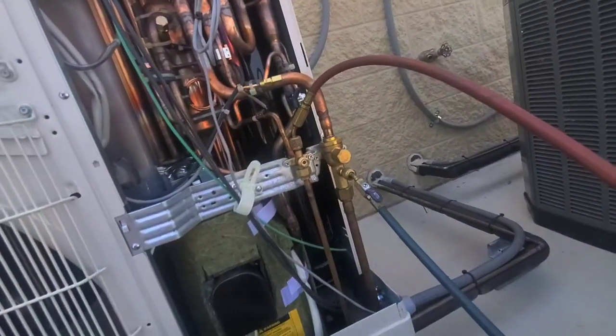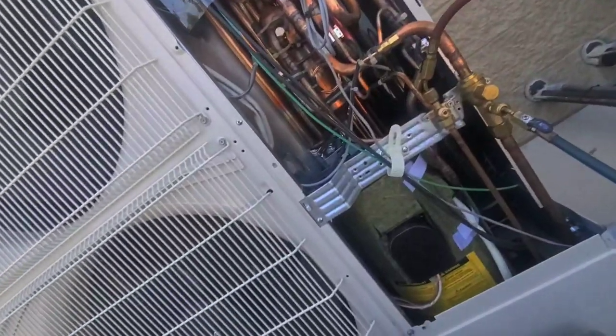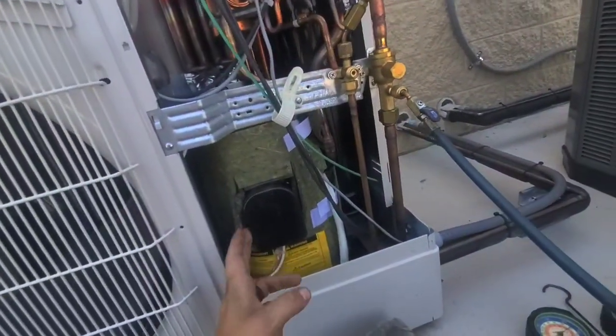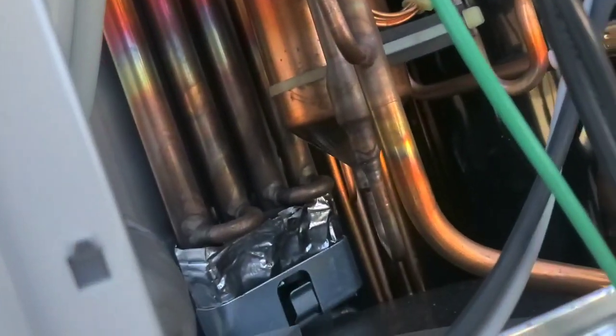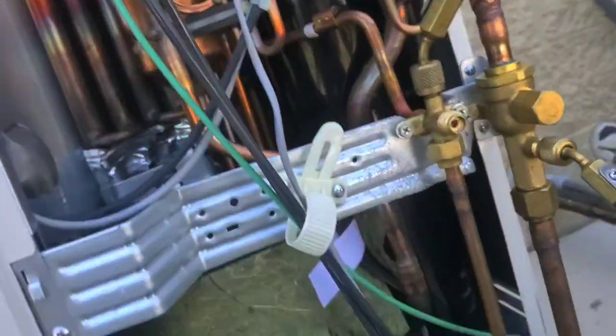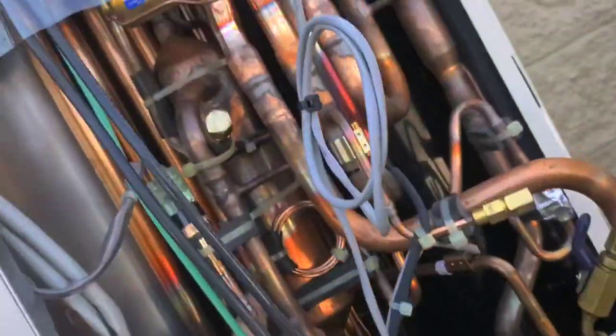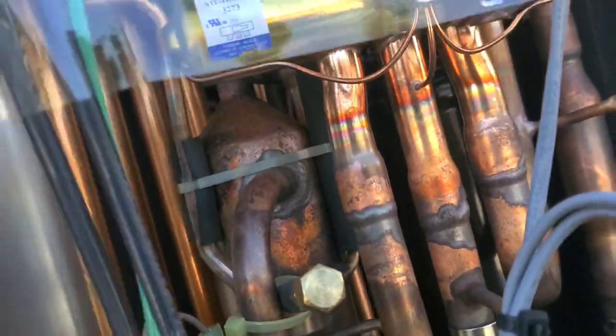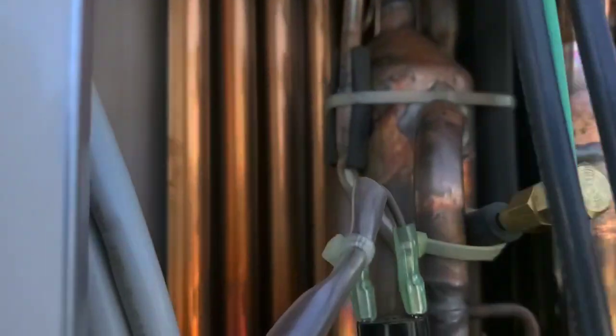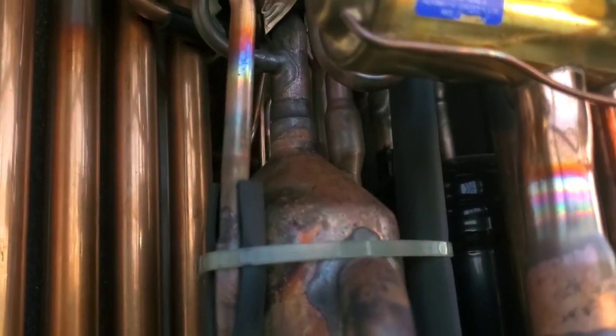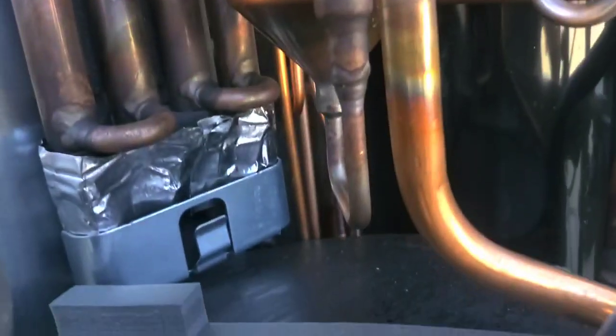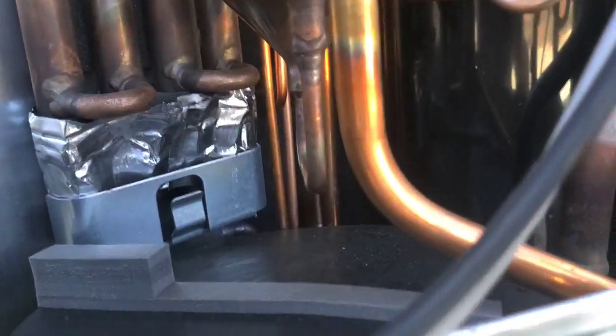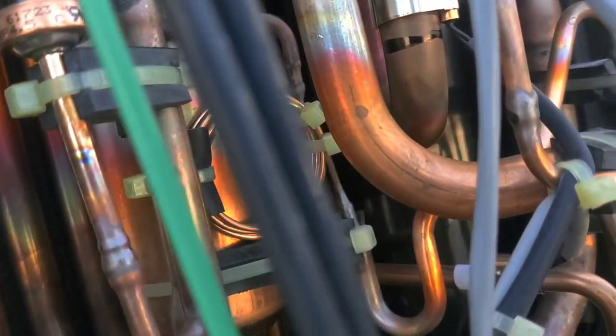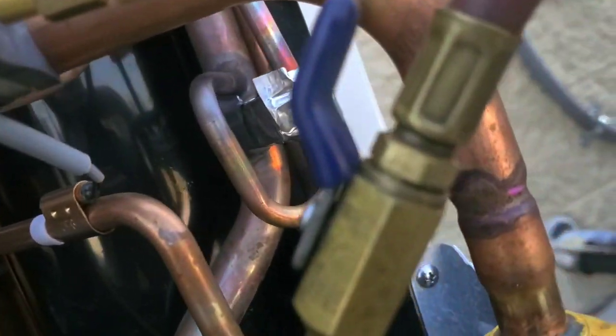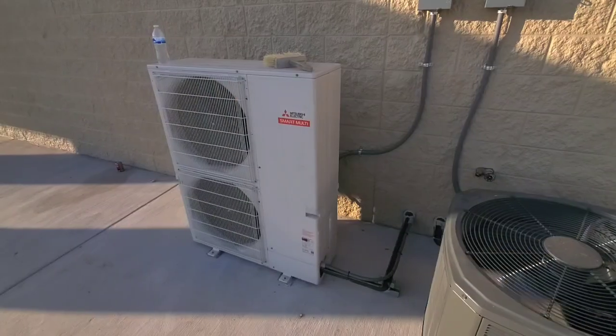You know, this will be ready to start up, except it's been less than 12 hours since I turned the power on. That's an oil separator. That's what that thing is. Discharge gas goes up this line and goes in here at an angle, spirals around. Eventually the gas goes out the top. The oil collects at the bottom where it goes through that capillary tube and into the suction line back to the compressor.